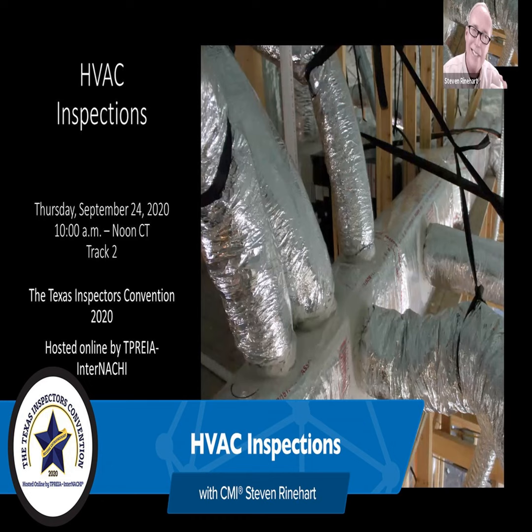And here, we'll talk about that highlighted one. That's the most contentious one. So inoperative units, kind of like a furnace. Turn the thermostat on cool, slap the gauge all the way down to the bottom, and wait. Most of them have a delay, and you wait. 20 minutes later, you notice nothing's happening. I've got a problem.